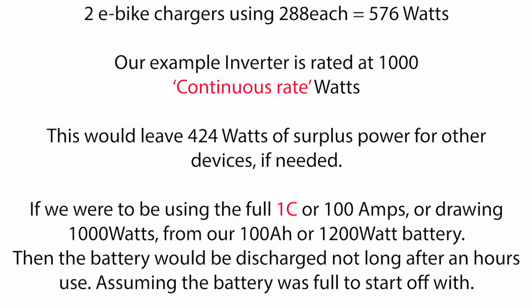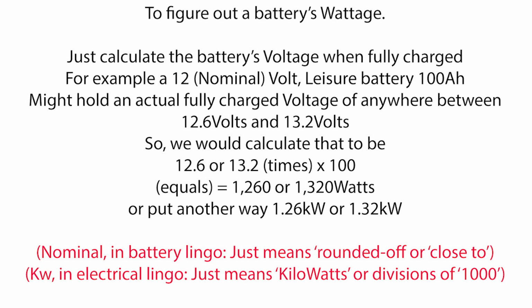Now, can my present 100 amp 12 volt DC battery handle the demands that the 1000 watt inverter might put on it? If that is, the full 1000 watts of AC electricity is actually being demanded from the inverter. An easy way to calculate what your leisure battery is capable of dishing out in the way of wattage is to simply multiply the battery output amperage by the nominal battery voltage. This is easy in my case. My battery is 12 volts at 100 amps, or 12 volts at 100 nominal amps. Nominal just being roundabout. It's a term used in the battery world to indicate a rough figure.